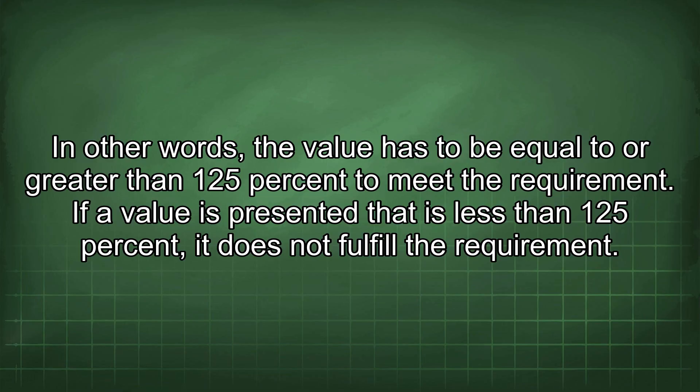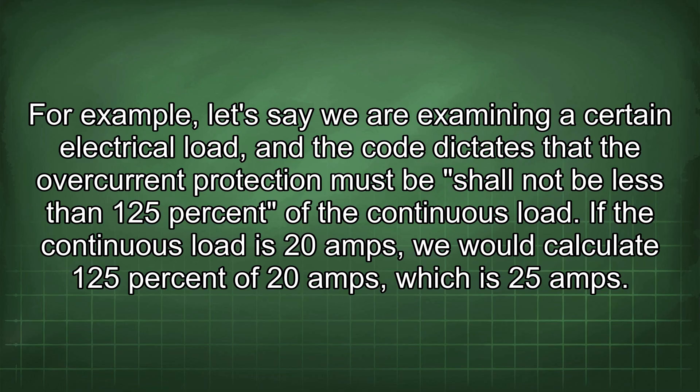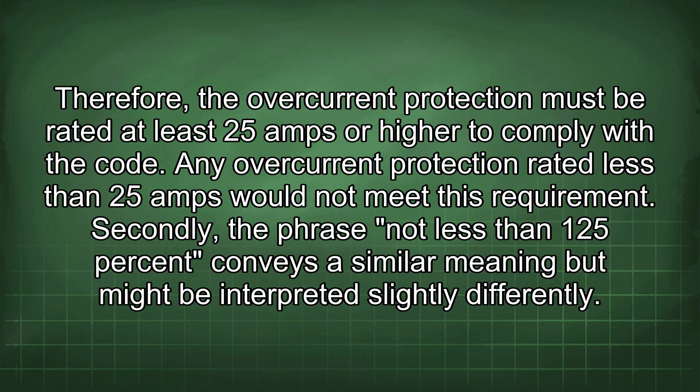If a value is less than 125%, it does not fulfill the requirement. For example, if we are examining a certain electrical load and the code dictates that the overcurrent protection shall not be less than 125% of the continuous load, and the continuous load is 20 amps, we calculate 125% of 20 amps, which is 25 amps. The overcurrent protection must be rated at least 25 amps or higher. Any overcurrent protection rated less than 25 amps would not meet this requirement.